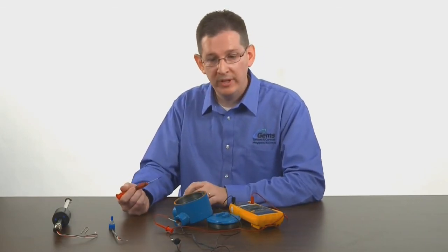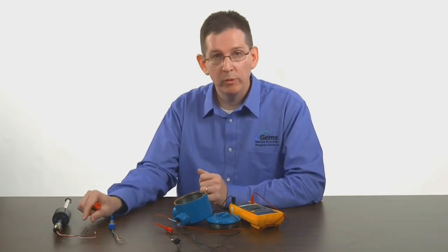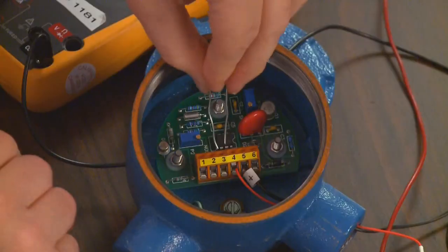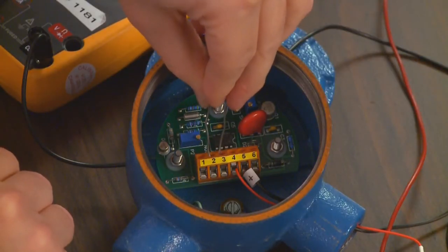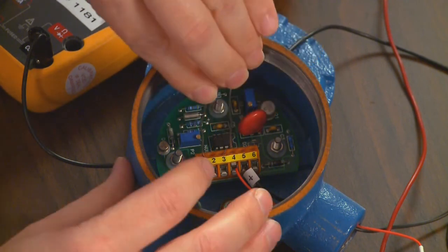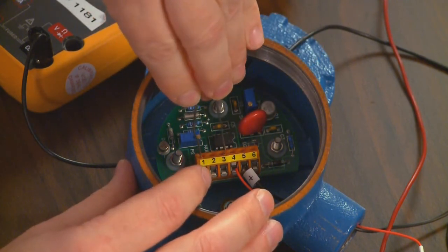If you do not have a potentiometer handy, you can replace that by using a simple jumper wire. Placing it from terminals 2 and 3 to set your 4 milliamp point, and 1 and 3 to set your 20 milliamp point.